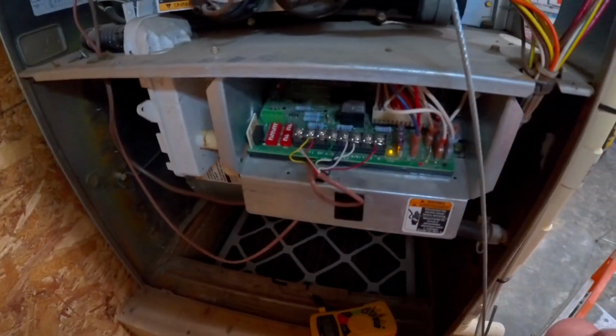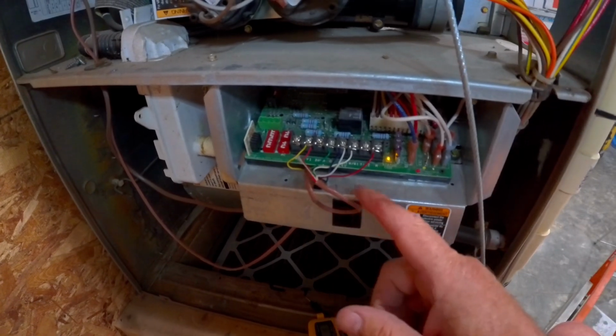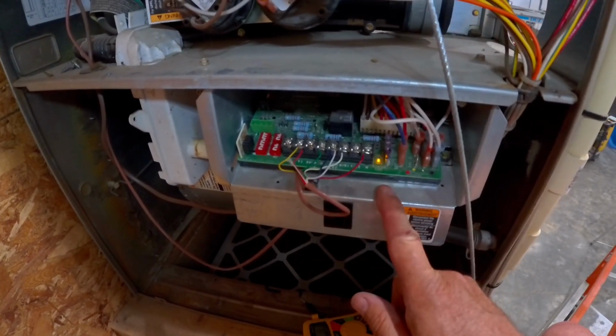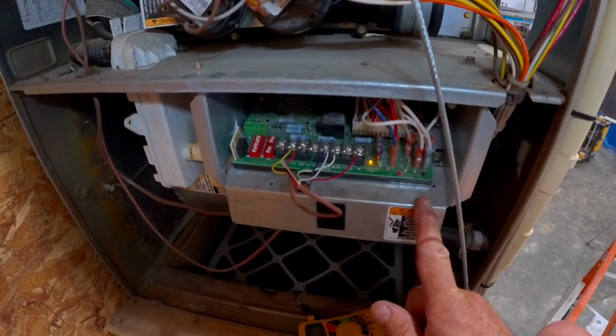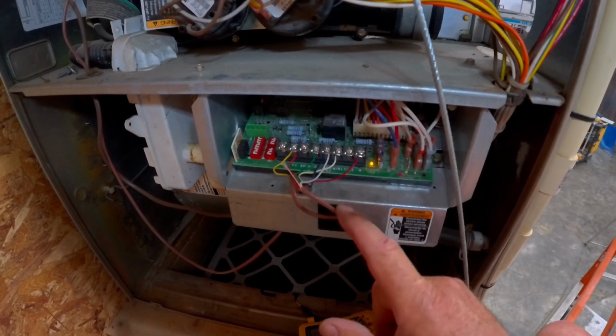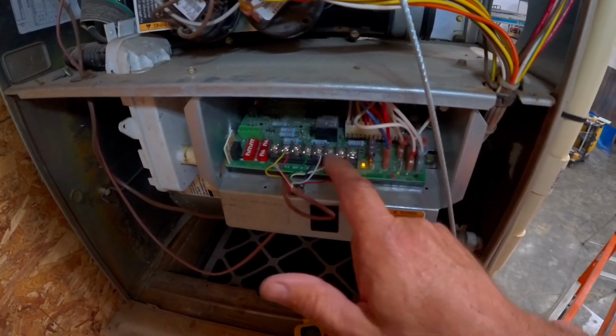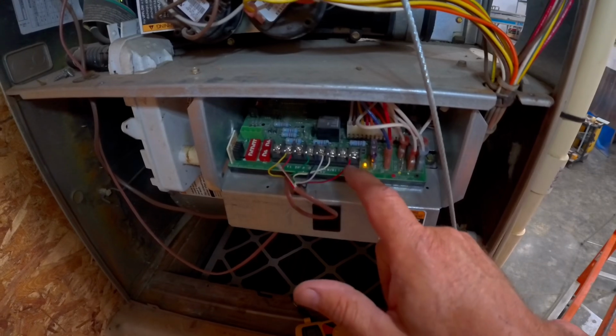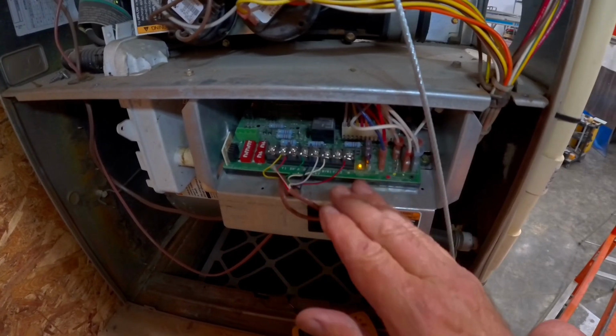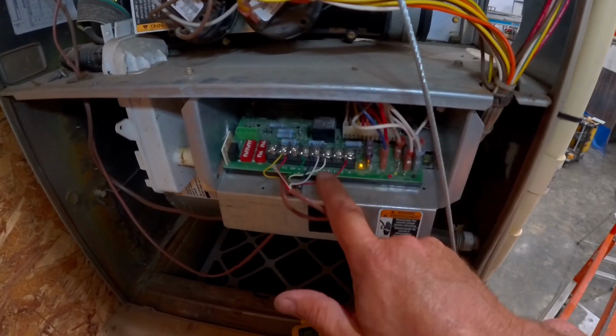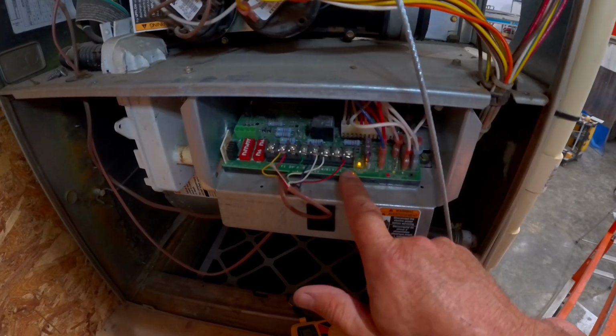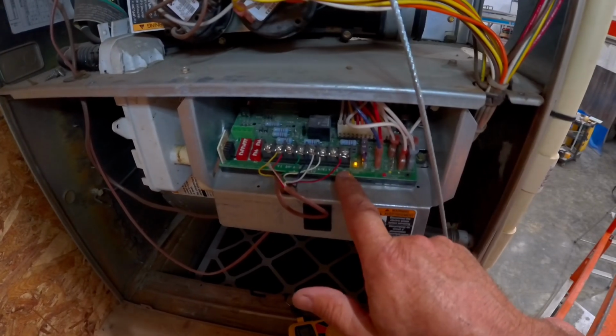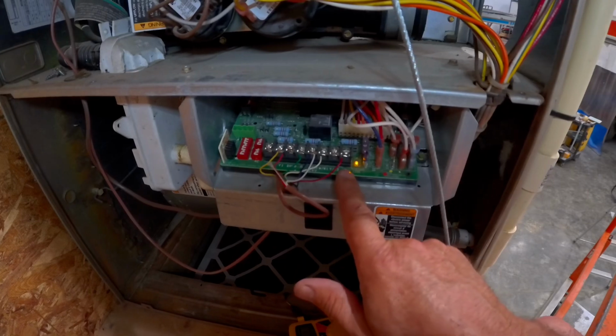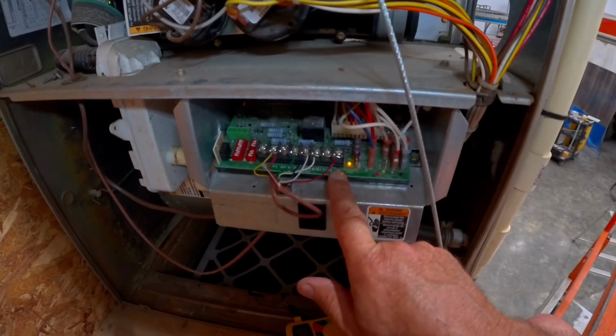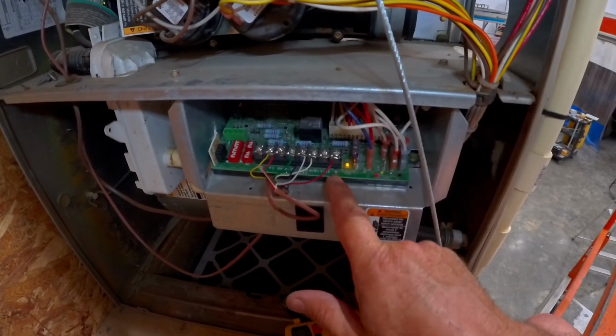The next step is we need to figure out if the thermostat is in fact telling the furnace to run and the air conditioning to run. And what we're going to do to verify that is check our voltages again at these terminals. This is where our thermostat wiring comes in and tells the system what to do. The wire that is connected to R is most commonly red. It's supposed to be red, but it doesn't have to be. It's all dependent on how your installer wired your system. But the standard in the industry is R is red.